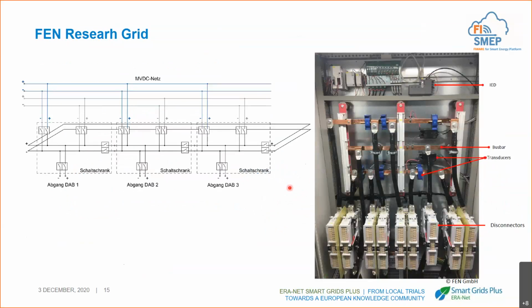For example, what we see here is a zoom of one of the buildings that we have. In particular, here we have a system of double bus bars and 3 different power converters that are connected in this point, which can be rearranged by commanding these switches. And here is a zoom of one of the panels that we have. In particular, we have the different disconnectors. We have the transducers that are the sensors that are measuring the current and the voltage that we want to virtualize with Fiware. And these analog measurements are collected by the IED, so the Intelligent Electronic Device.